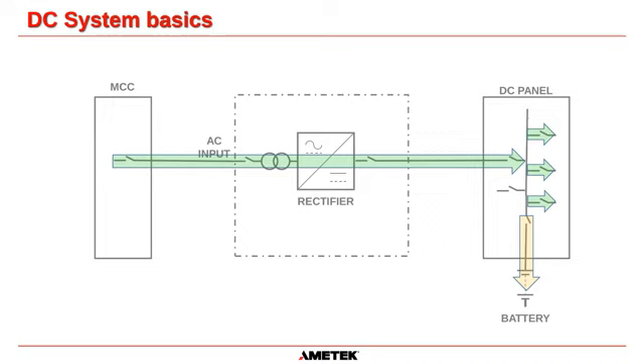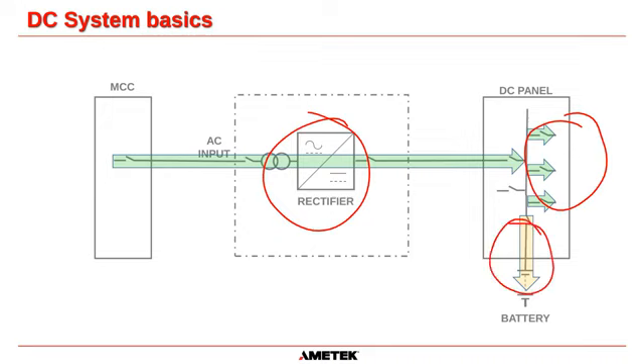This arrangement here is much easier to maintain. It allows you to take the battery out of service if absolutely necessary, or add a temporary battery into the system if you want, without losing any of your loads. It's just very versatile. So this is the best designed DC system as far as we're concerned anyway. So that is the basics of a DC system. You can see there's the charger there, there's your load circuits there, and there's your battery connected there. And they all have isolation points. There's an isolation point there, an isolation point there, and there's a DC battery breaker there.